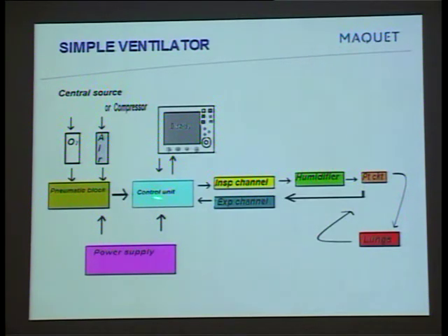Now you have given certain inputs: I want to deliver a certain amount of volume, pressure and flow. The machine will accept that, and then it will give the instruction to the pneumatic block. The pneumatic block will then release whatever volume, pressure or flow you want to deliver.